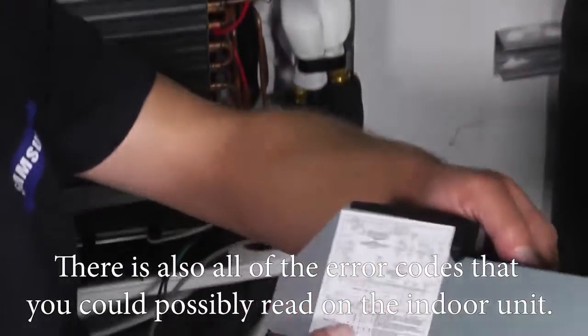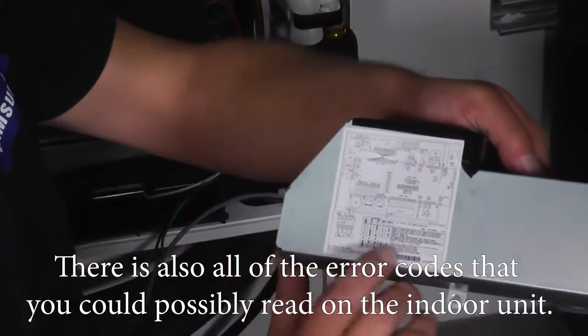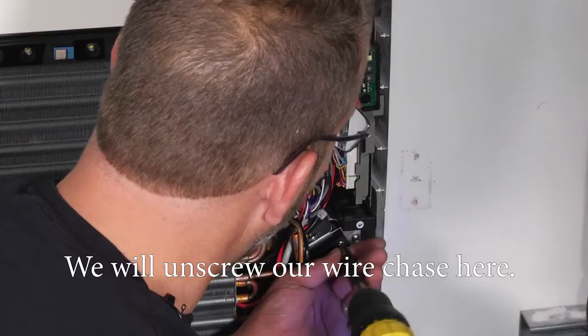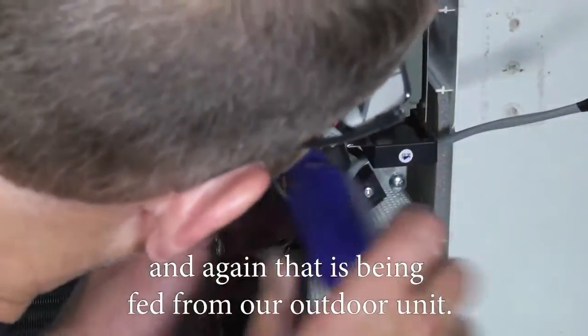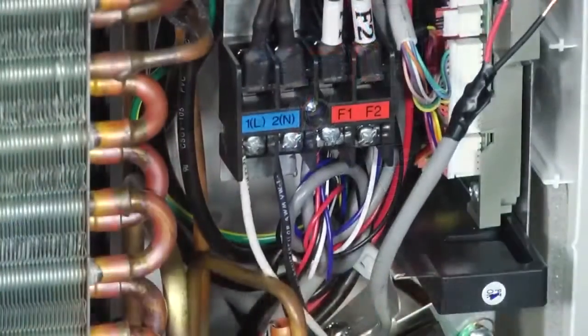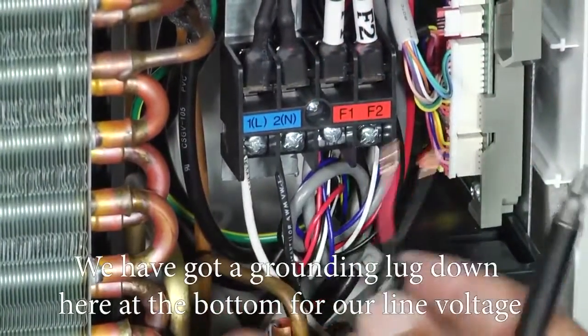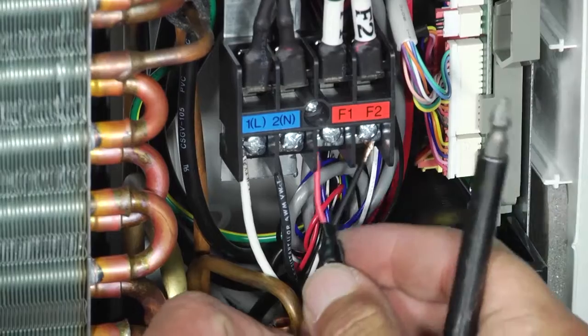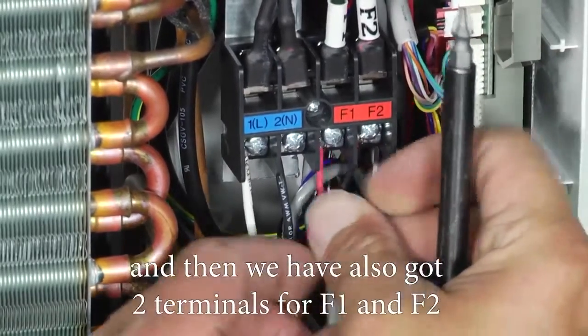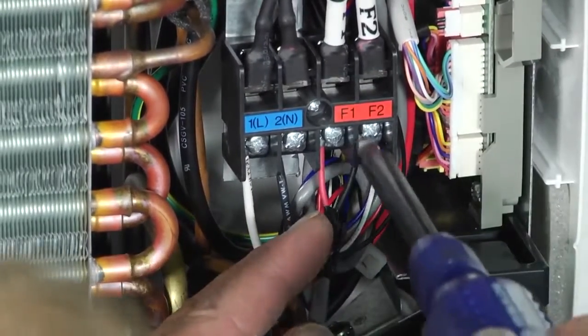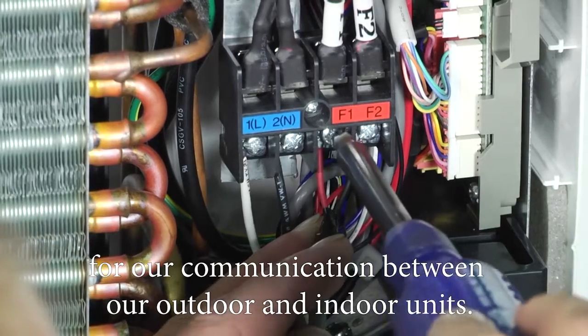There's also all the error codes that you can possibly read on the indoor unit. We'll unscrew our wire chase here. So we've got a terminal block that's got a 1L and a 2N for our high voltage. And again, that's being fed from our outdoor unit. We've got a grounding lug down here at the bottom for our line voltage. And then we've also got 2 terminals for our F1 and F2 for our communication between our outdoor and indoor units.